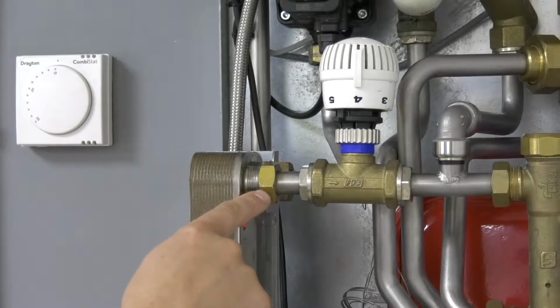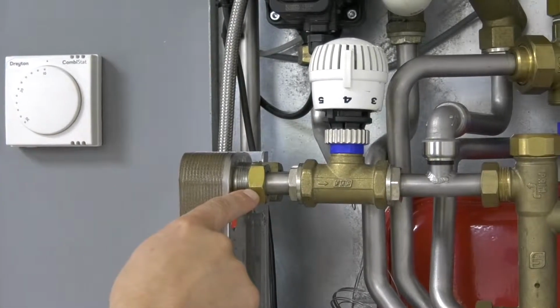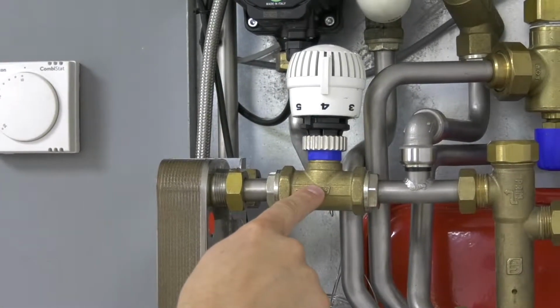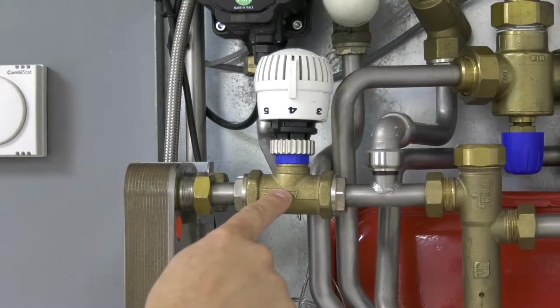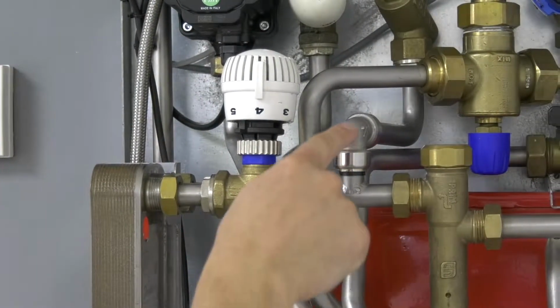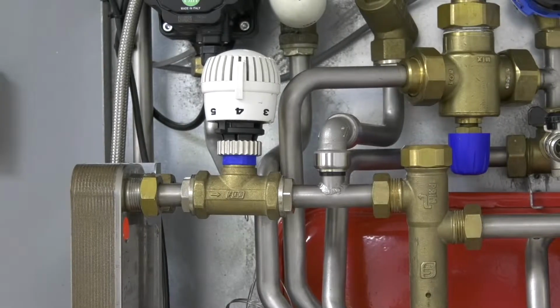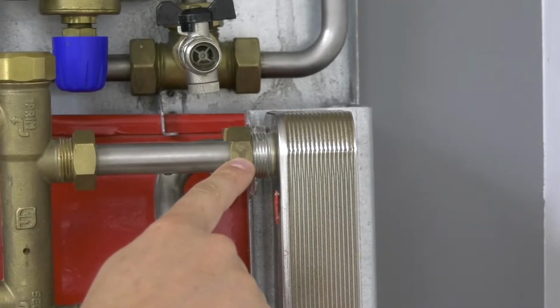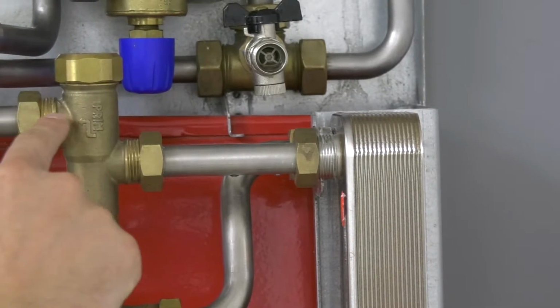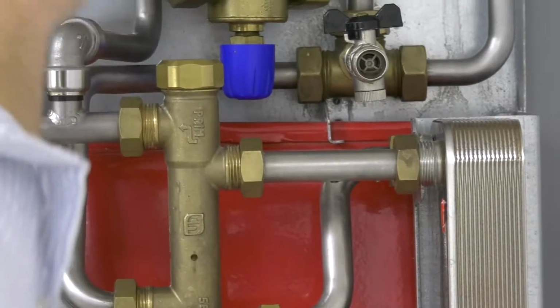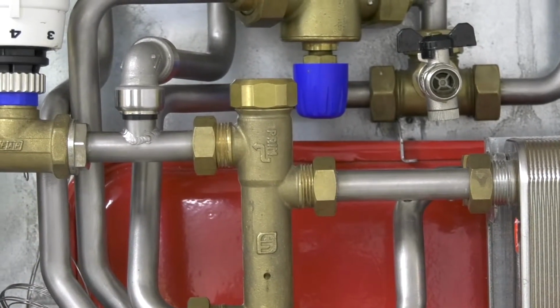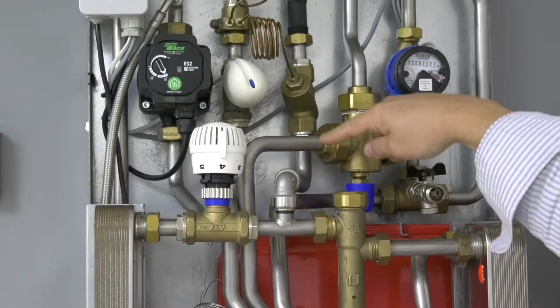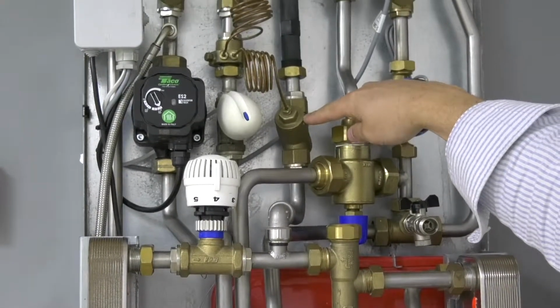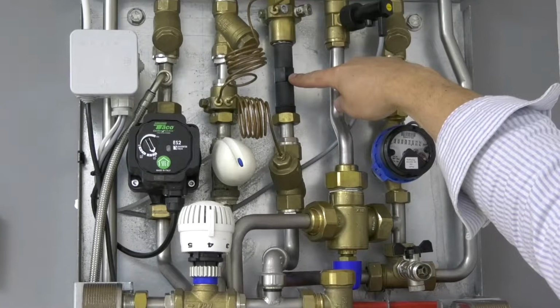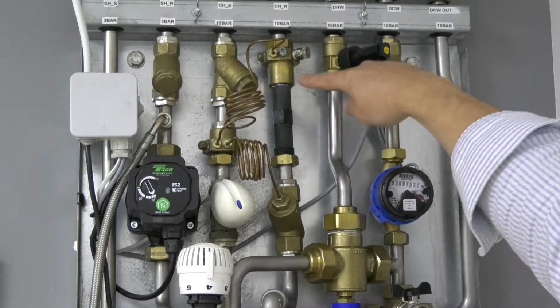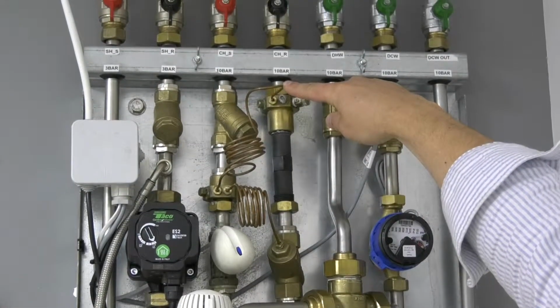At the top of the plate heat exchanger you have the heating primary outlet and the thermostatic valve teeing off to the return. To the other side at the top of the hot water plate heat exchanger you have the outlet through the proportional valve to the primary return. This feeds up through the differential pressure control valve, the connection for where the heat meter sits, and the trickle bypass connection to return to the system.